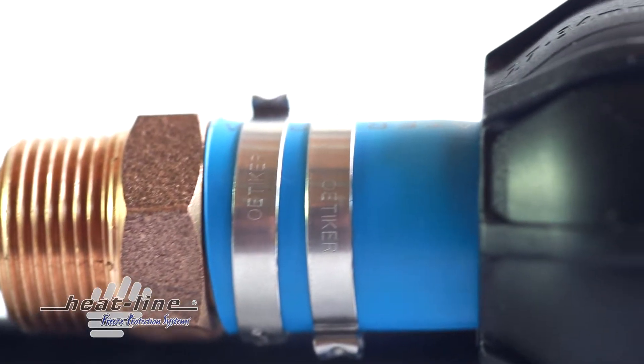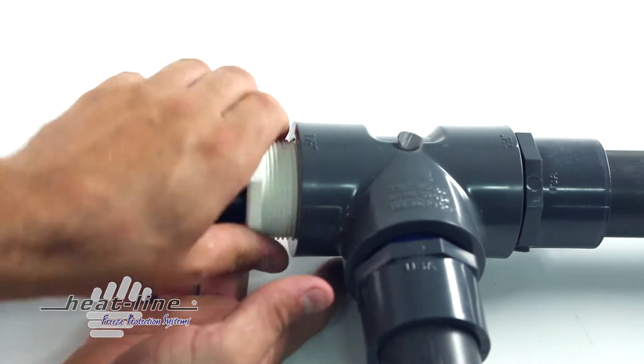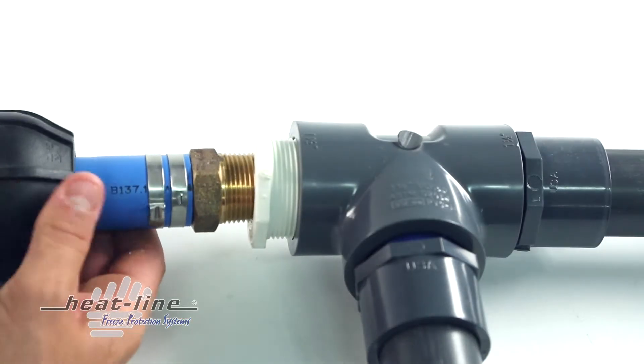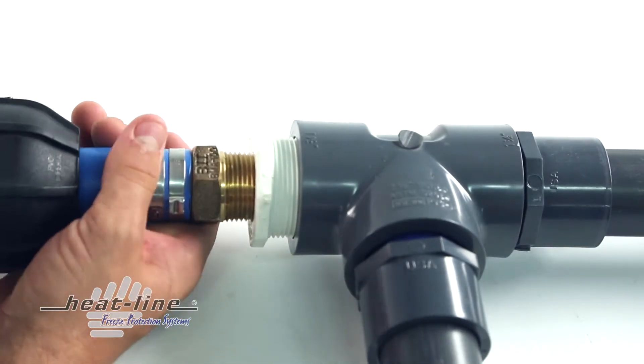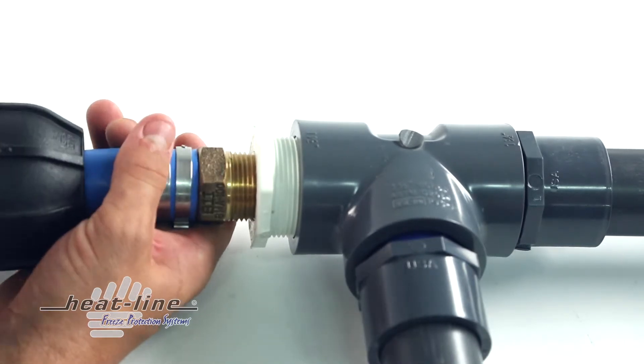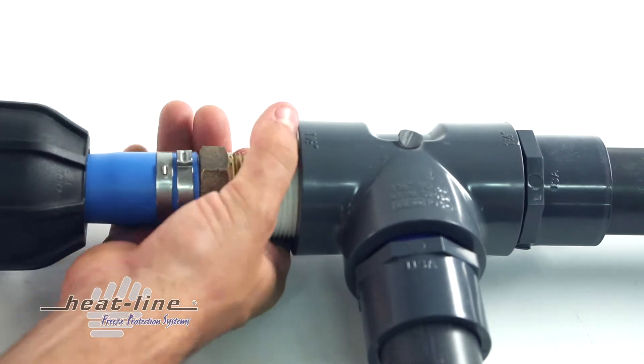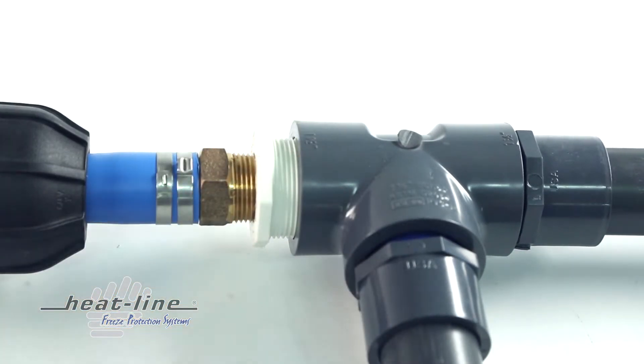RetroFM is supplied job ready with a 1-inch brass MIP male threaded adapter fitting and a 1-inch FIP female threaded adapter by 2-inch MIP male threaded adapter PVC reducing bushing. This allows the RetroFM to quickly interface with 1-inch and 2-inch force main T or Y fittings. The RetroFM is also able to adapt to large diameter pipes given the versatility of its MIP male threaded adapter connection.